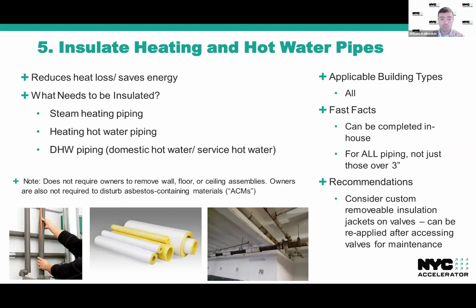So this measure is going to apply to steam heating piping, heating hot water piping, and domestic hot water piping. It's not going to require that you open up any walls or assemblies or ceilings to access uninsulated pipes. And you also do not have to touch pipes that contain asbestos, but all other pipes, no matter the size, are going to need to be insulated. This is applicable to all building types.